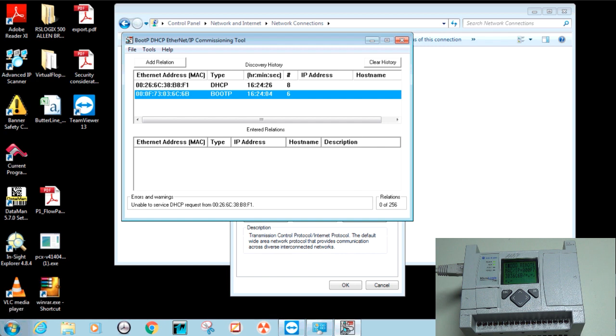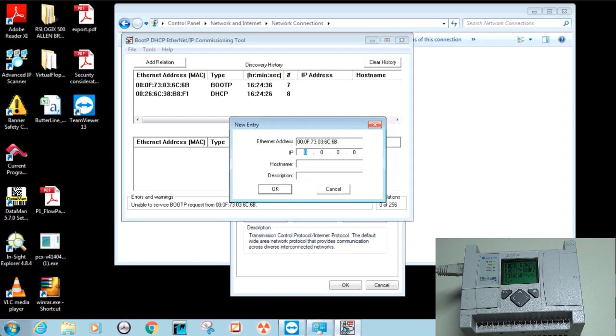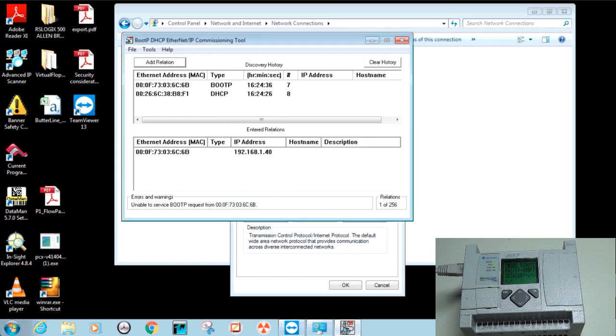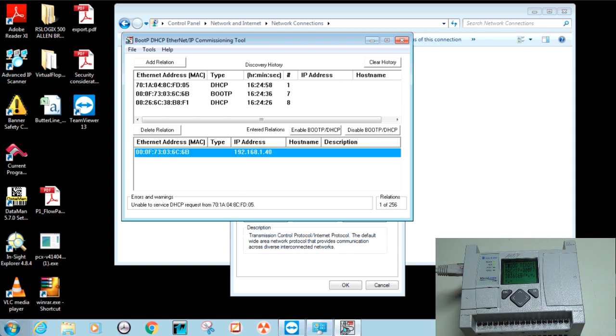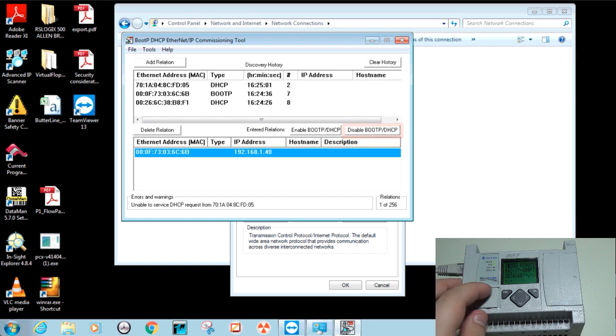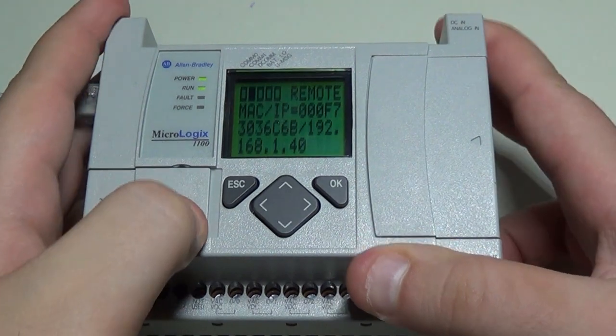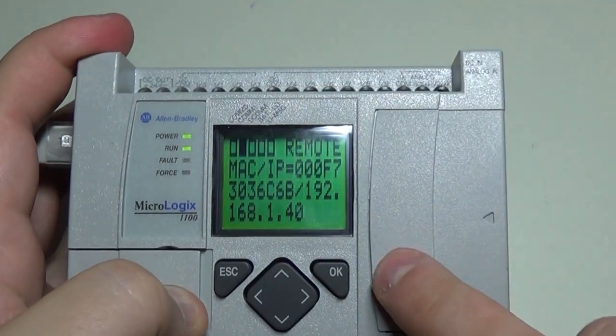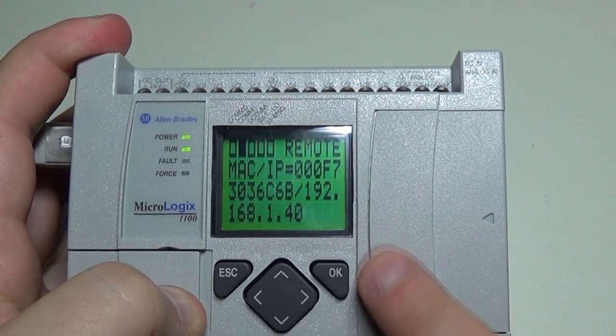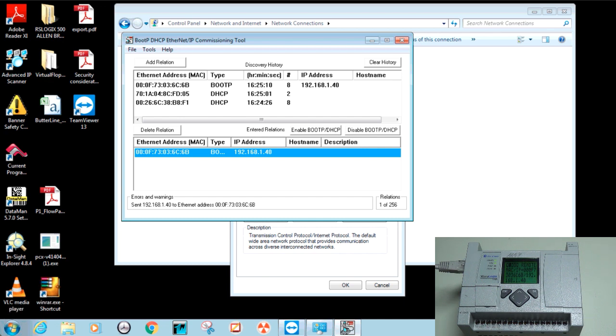Once you identify the correct MAC address row, hit 'Add Relation' where you can set an IP address for your PLC. I'm putting it on the local subnet: 192.168.1.x — let's say 40 — then hit OK. The IP address is now set in BOOTP but not yet on the PLC side. You then need to hit 'Disable BOOTP', which tells the PLC to retain the IP address rather than requesting one on every boot. You should see the IP address update on the PLC's LCD screen, confirming it has been properly set. You can now close the utility.